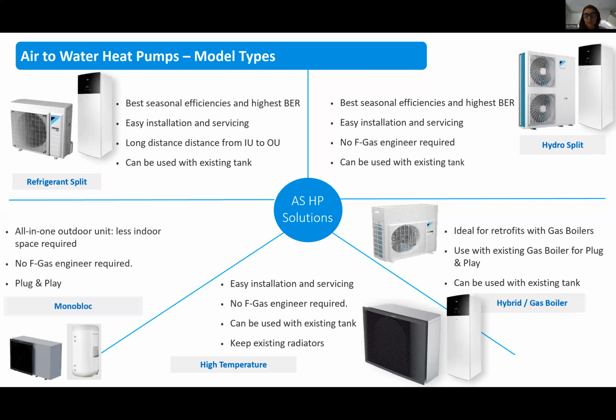But going back to the monoblock, it would be one of the most popular models available on the market. So for anybody coming into heat pumps for the first time, this is a really good option. There's no F-gas requirement. All of the components are built into the outdoor unit. You'll notice that the outdoor unit is usually longer than a split unit because all of your hydraulic and electrical components are built into the outdoor unit. And from that, you just take your connection into the house, into a three-port valve to divert between heating and hot water, and then onto your cylinder. So it's a very nice starter product for anybody getting into air-to-water heat pumps.